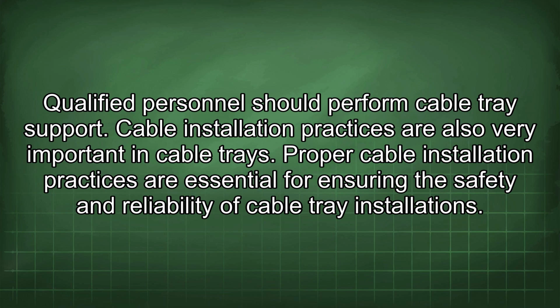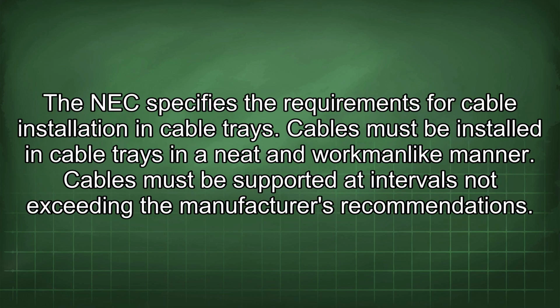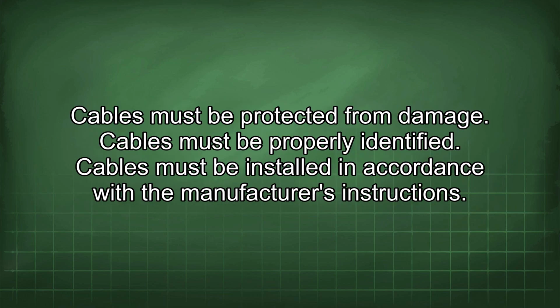Proper cable installation practices are essential for ensuring the safety and reliability of cable tray installations. The NEC specifies the requirements for cable installation in cable trays. Cables must be installed in cable trays in a neat and workmanlike manner. Cables must be supported at intervals not exceeding the manufacturer's recommendations. Cables must be protected from damage. Cables must be properly identified. Cables must be installed in accordance with the manufacturer's instructions.